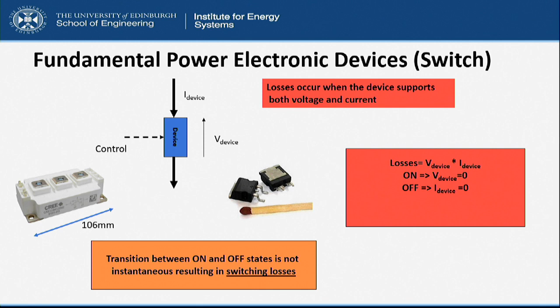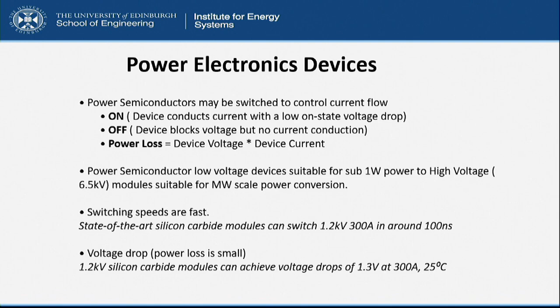The types of rating we can achieve go up to 6.5 kilovolts for high power applications. Switching speeds can be really fast. If we take the really modern devices, you can be switching 1.2 kilovolts at about 100 nanoseconds. And the voltage drop is low. A device that can block 1.2 kilovolts only has about 1.3 volts across it when it's on. So you're not losing much power in the device. It's significant in terms of heating the poor little bit of silicon, but not significant in terms of the total power throughput we could get.